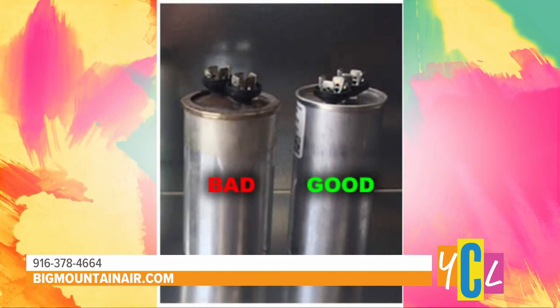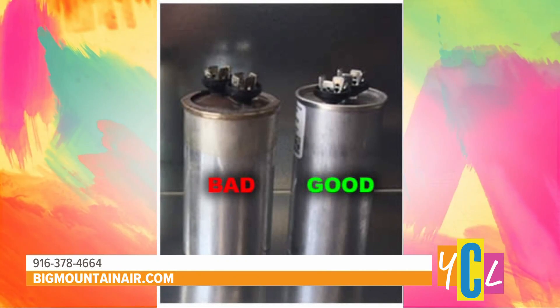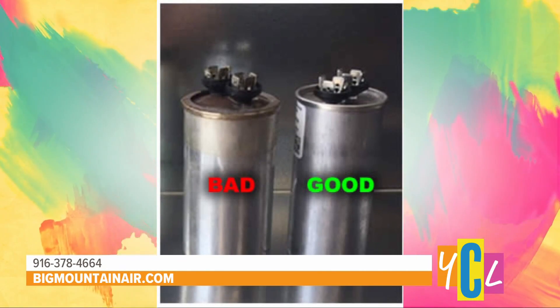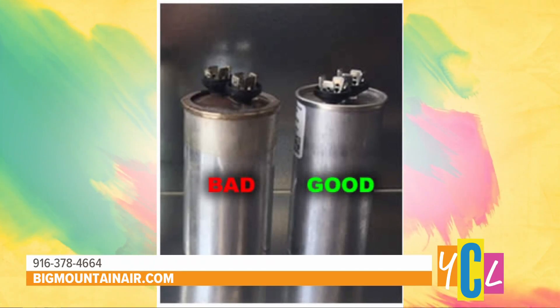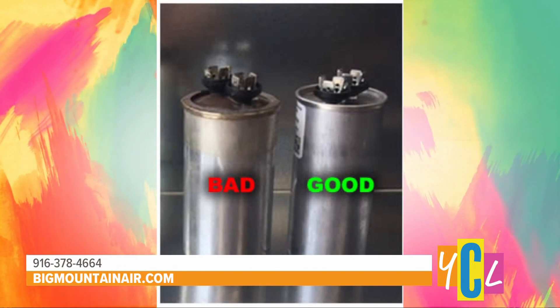Well, here's the culprit right here. Pretty benign-looking little part, but it's really the part that fails the most, especially in the extended heat cycles like we're going to have with this heat wave coming up over the weekend. There are essentially two types of these capacitors — one of them, as you can see, is marked good and the other is bad. You can hardly tell.